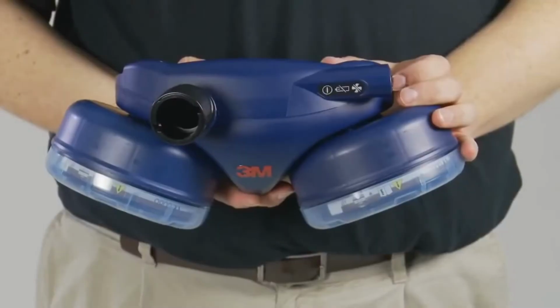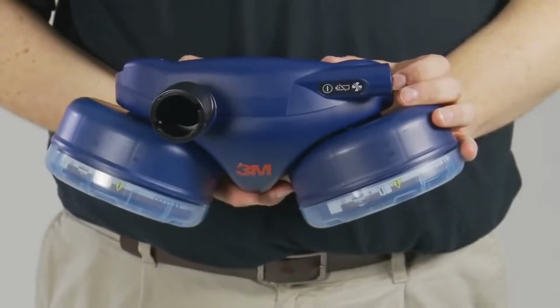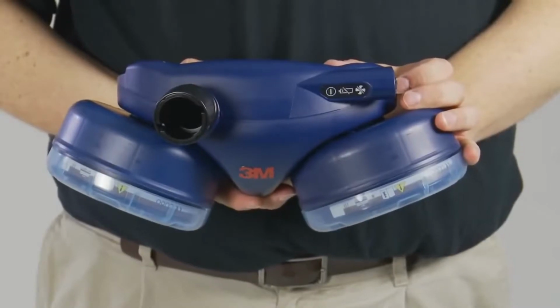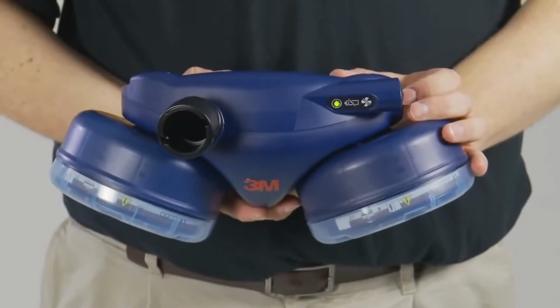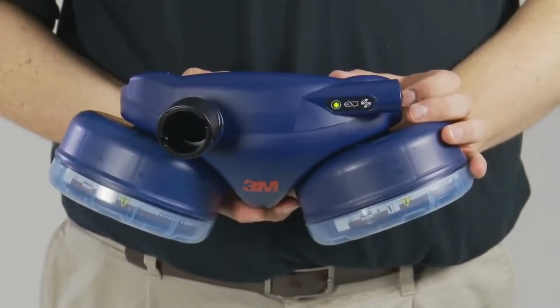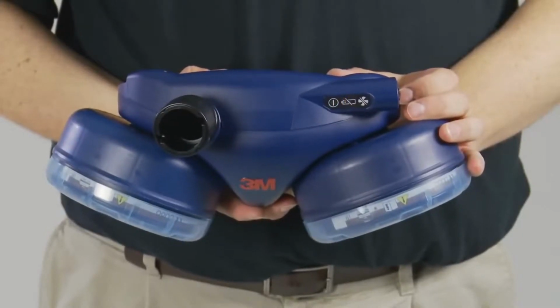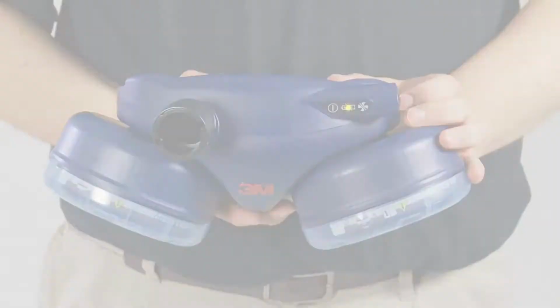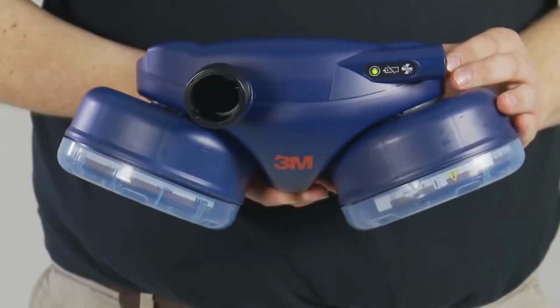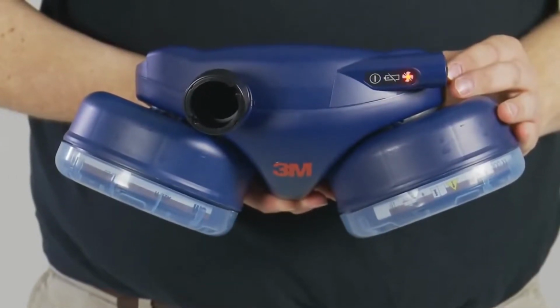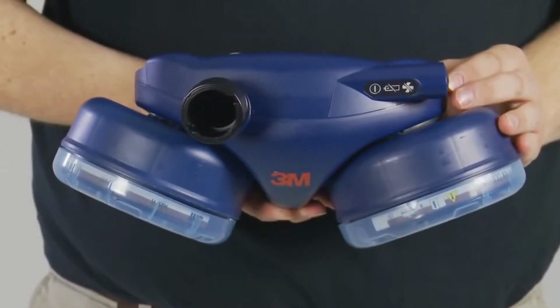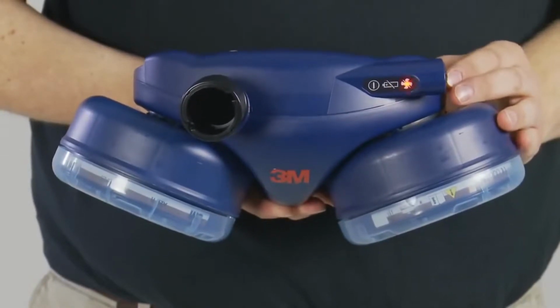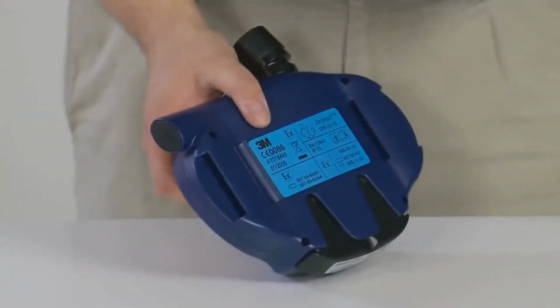When in use, it is easy to identify the cause of an alarm. If you see a green flashing light, then the unit is working correctly. A flashing battery light accompanied by a long intermittent beep means a low battery alarm. A flashing fan light accompanied by a long intermittent beep means that the flow is approaching or is below manufacturer's minimum design flow rate due to clogged filters or obstructed hose.